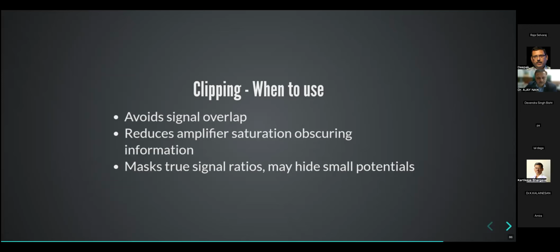So for example, you put a pacing spike. When you put a pacing spike, that's a very high voltage signal. Now the amplifier, when it pushes it up that much, for it to get back to a lower level and be able to see a signal that comes after pacing will take some time. And this you will see on the signal. I don't have an electrogram here to show that, but you'll see it as a sort of plateau after your pacing spike. It tells you that the amplifier is saturated, and this saturation can be reduced by clipping it. If you clip it, you tell the amplifier, even though the signal is going above 5 volts, you don't need to push your output that much. So that helps you see the smaller signals which come later.